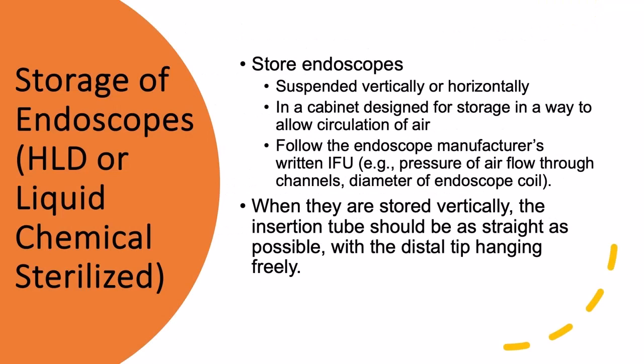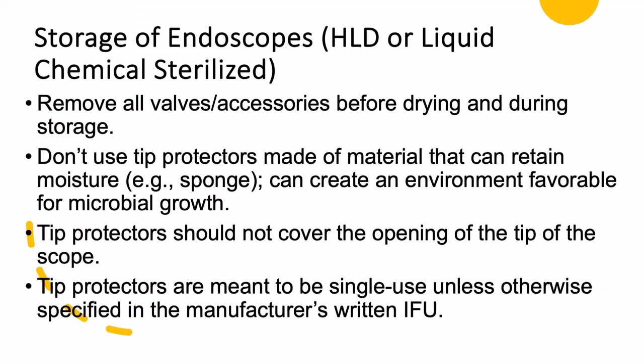For storage of high-level disinfected or liquid chemically sterilized endoscopes, you're going to store them vertically or horizontally. There is a cabinet that does allow you to store them horizontally. In a cabinet designed for storage in a way to allow circulation of air, and follow the endoscope manufacturer's instructions for pressure of airflow through the channels and the diameter of the endoscope coil. When they are stored vertically, the insertion tube should be as straight as possible with the distal tip hanging freely. Remove all valves and accessories before drying and during storage.